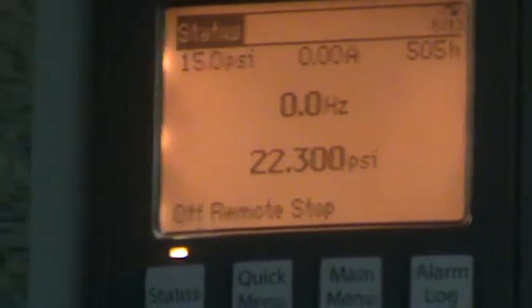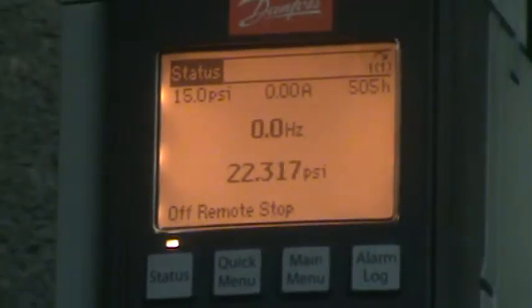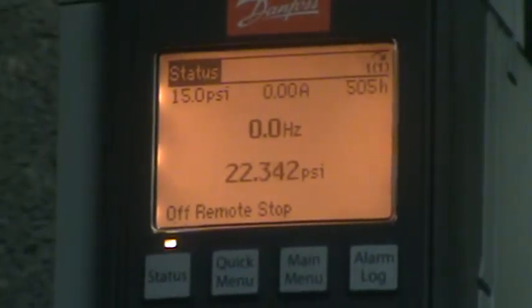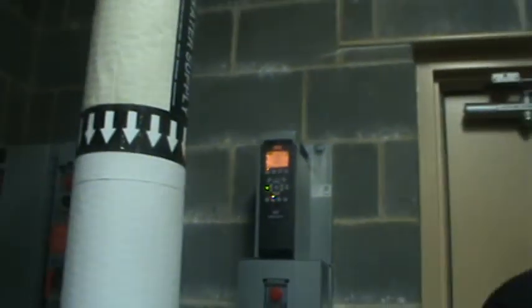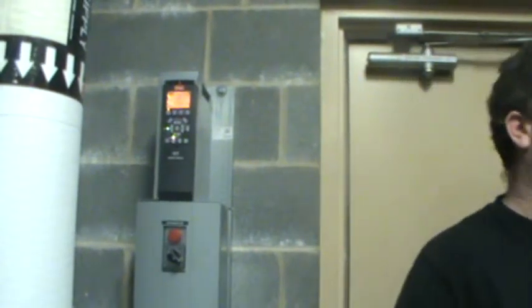But they're plain English. They're high current, low current. The low current will just shut down. Phase loss, main phase loss. One that confuses a lot of guys, which probably, let you guys know: there's two different phase loss alarms you can get. If you ever see one, read it very carefully. It'll say main phase loss or phase loss. Main means from here to wherever the power came from. Phase loss means from here to there. It'll actually tell you what leg of power is missing.